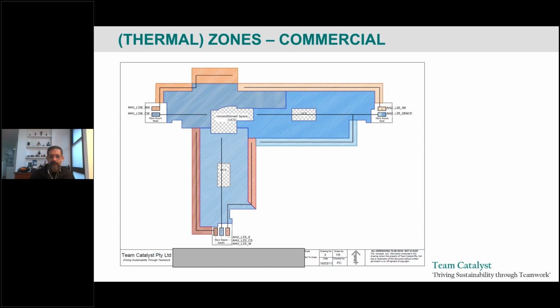In the morning, the east zone will need more cooling because that's where the sun hits the wall. In the afternoon, the west zone will need more cooling, since that's when the sun hits it. The internal zone may not change much if it's an office-type building. So this zoning is quite important, and it's a kind of dance between the architect and the mechanical engineer to decide how the building works.